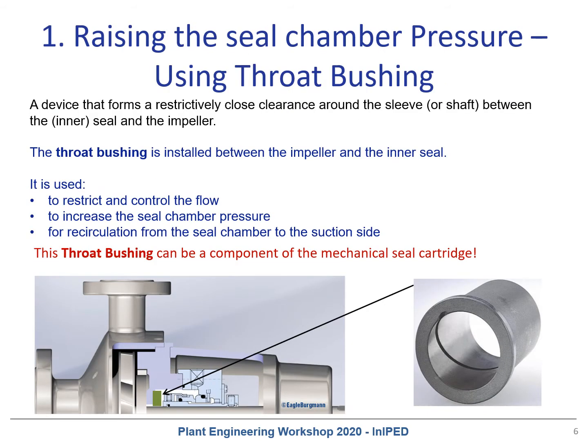Some details on option one: raising the seal chamber pressure by using a throat bushing, which is a device that forms a restrictively close clearance around the sleeve or shaft between the inner seal and the impeller. The throat bushing is installed between the impeller and the inner seal, used to restrict and control flow, increase the seal chamber pressure, or allow recirculation from the seal chamber to the suction side of the pump. This throat bushing can also be a component of the mechanical seal cartridge.